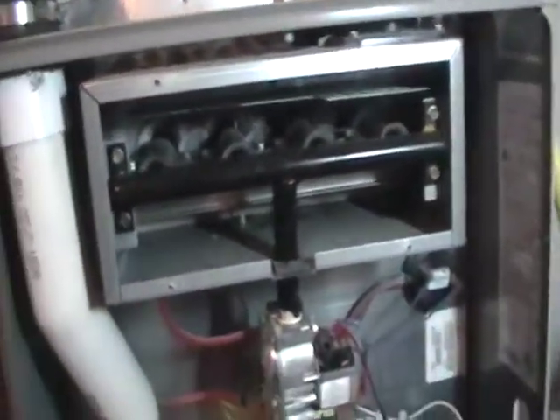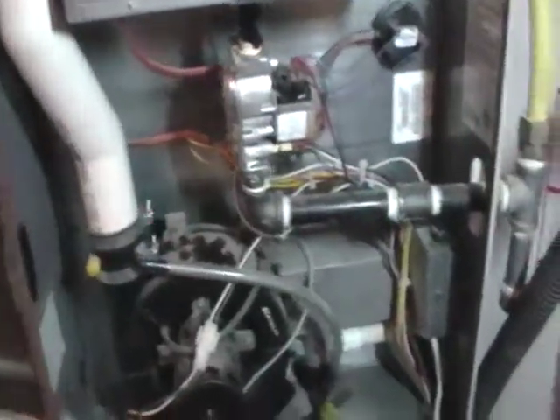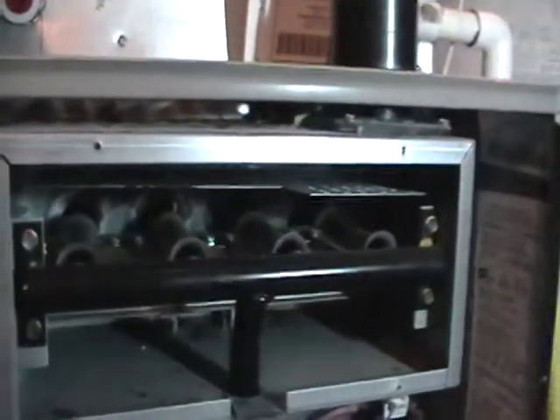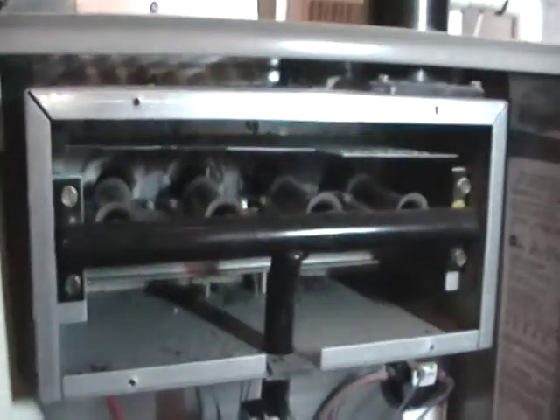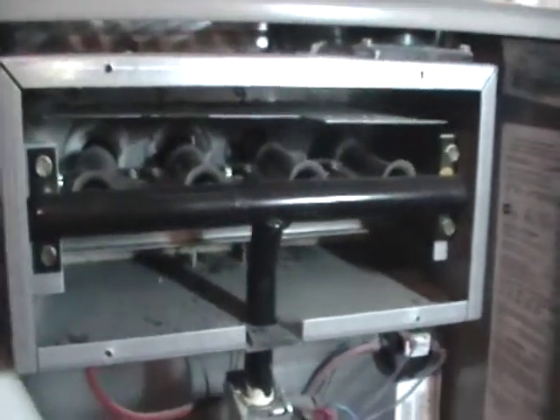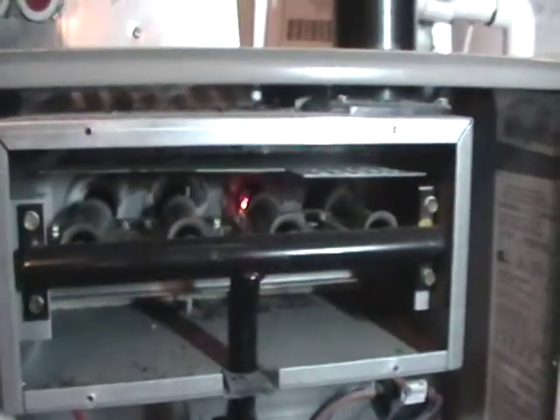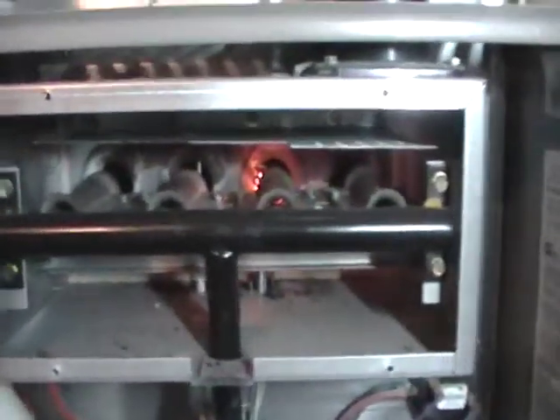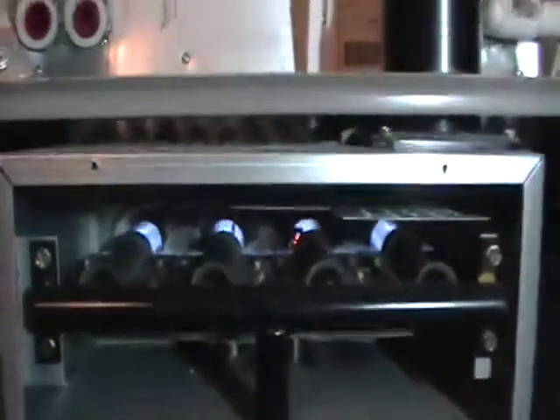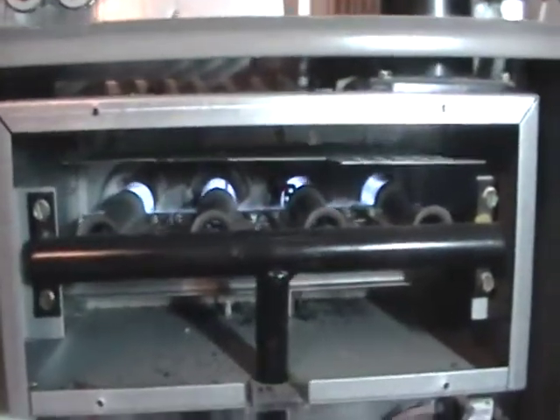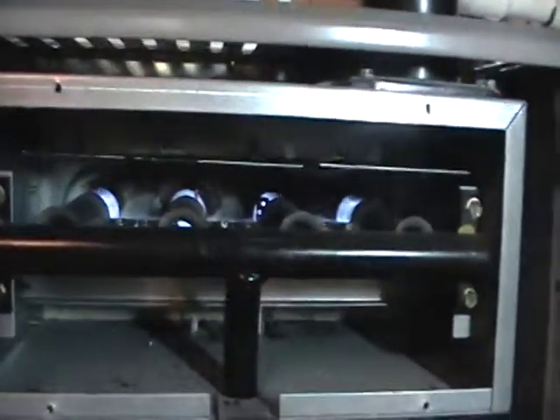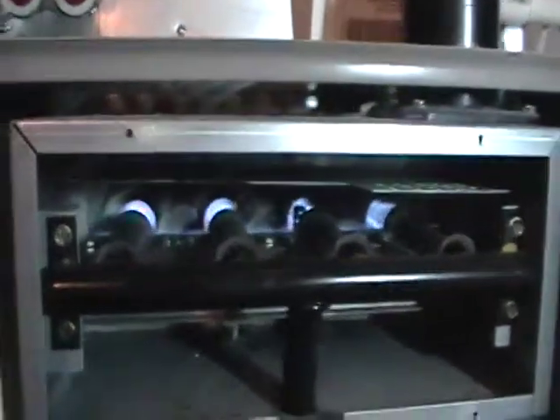Now again, we'll watch the cycle of the furnace. Venter motor is going to come on. The hot surface igniter is going to start to glow. Then the gas valve will give the burners gas, and the flame is proved across the flame rod. Now you want to make sure that that is a steady process. It doesn't cycle, turn on and off. The flame looks like it's stable, not a lot of yellowing in the flame, and when the furnace fan kicks on, you don't see a big wave in the flames.